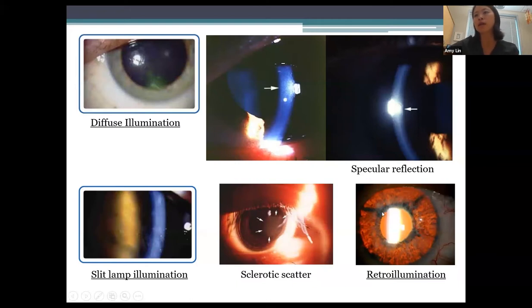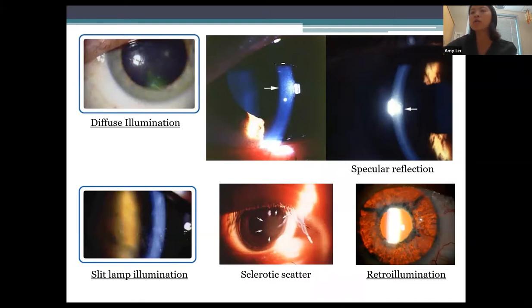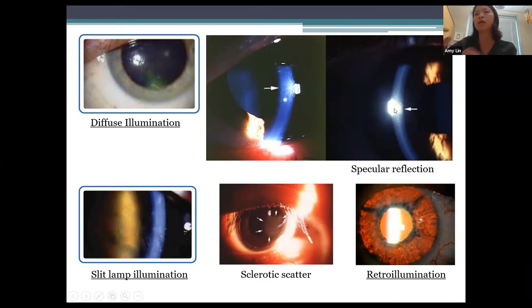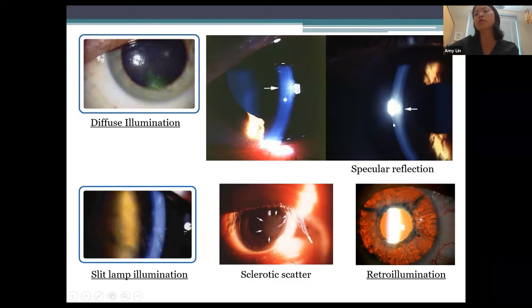Other techniques I use less often include specular reflection, which examines tissues around normal light reflexes, especially the posterior corneal surface. You use a very small intense slit beam at a 60-degree angle from the viewing arm, superimposing the posterior corneal light reflex with the bright slit lamp light bulb reflex. Then you move the joystick forward slightly to look at the posterior corneal surface, and at high magnification you can see subtle endothelial findings.